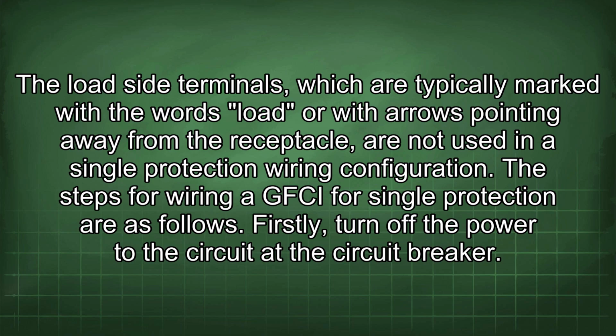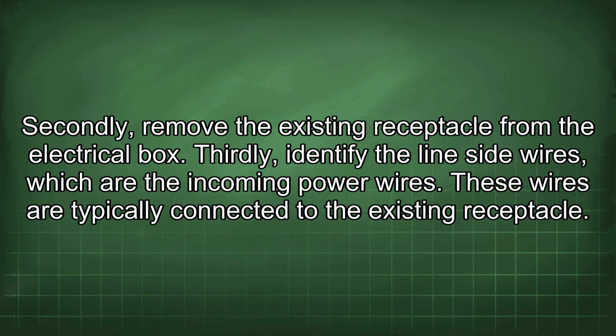The steps for wiring a GFCI for single protection are as follows. Firstly, turn off the power to the circuit at the circuit breaker. Secondly, remove the existing receptacle from the electrical box.